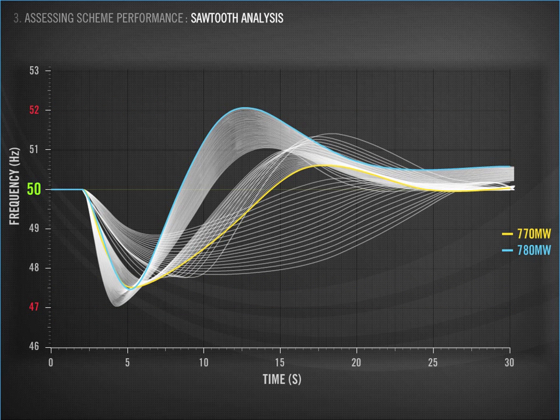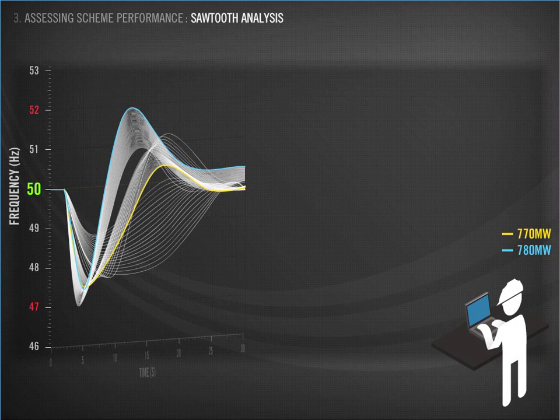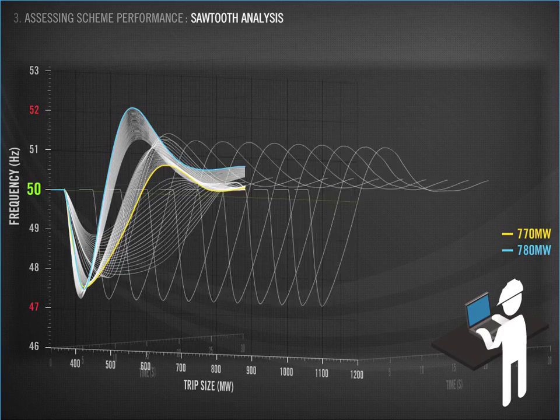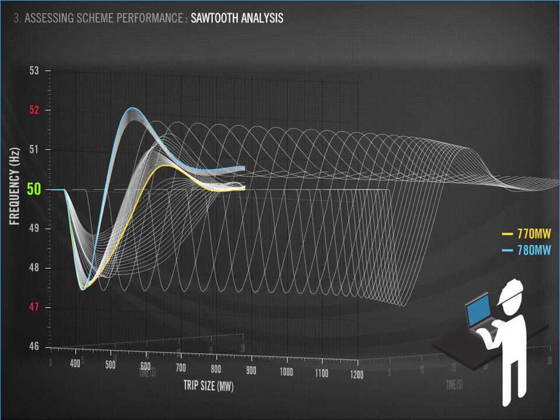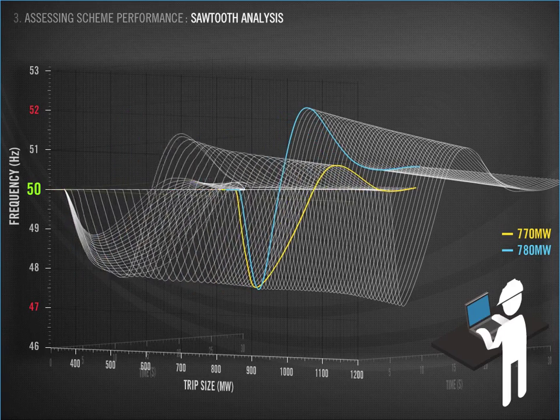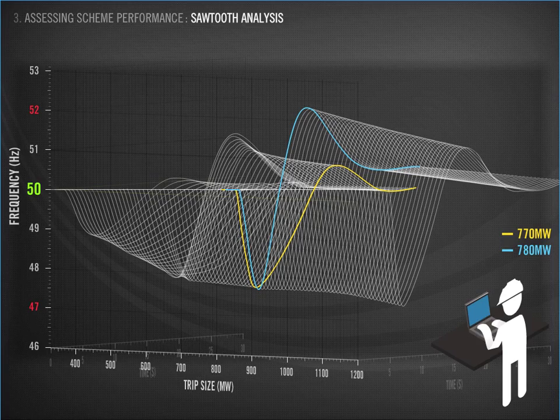The engineers identified two key performance indicators: What was the minimum point that the frequency reached? And what was the maximum point that it reached following UFLS operation? By adding trip size to the equation, they were able to see how big the event was and how the system responded. The graph starts to tell more of a story.